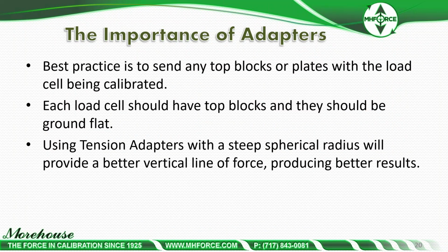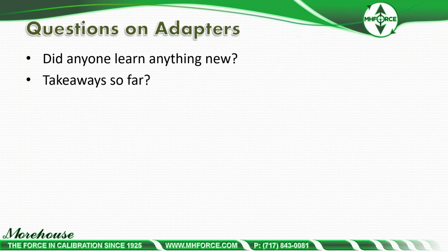Best practice, importance of adapters. Best practice is to send any top blocks or plates with the load cell being calibrated. Each load cell should have top blocks and they should be ground flat. Using tension adapters with a steep spherical radius will provide a better vertical line of force, producing better results.